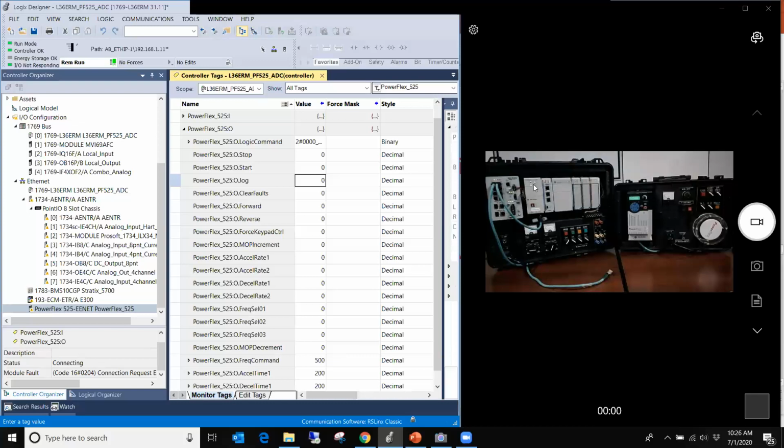The controller will realize it has a device, it is authenticated, but the checksum is different, so it knows the parameters are different, so it will then send over a set of parameter files. But before it does, it doesn't know what this drive really has in it other than the checksum is different. So it will reset this drive back to factory defaults, and you'll see the drive fault. The controller will then clear the fault and then send down its host list of parameters.